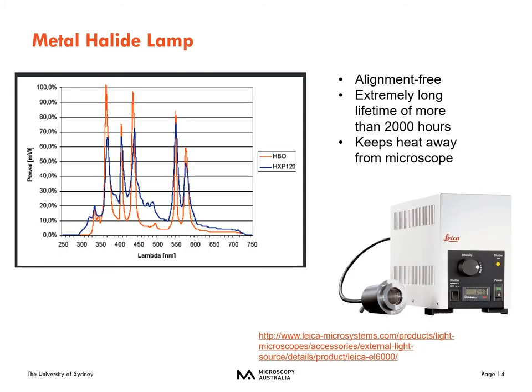More popular now is the metal halide lamp. It has a very similar spectrum to the mercury lamp, but is a little bit nicer because it typically has a light fiber guide making alignment trivial. It has an extremely long lifetime — more than 2,000 hours. It keeps heat away from the microscope and has a shorter warm-up and cool-down time of about five to ten minutes.